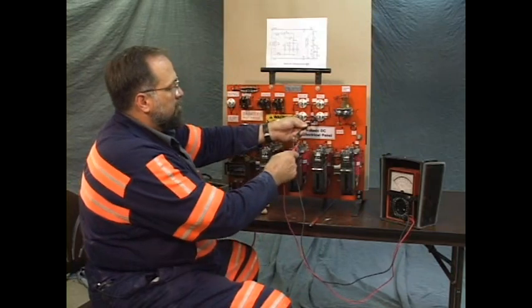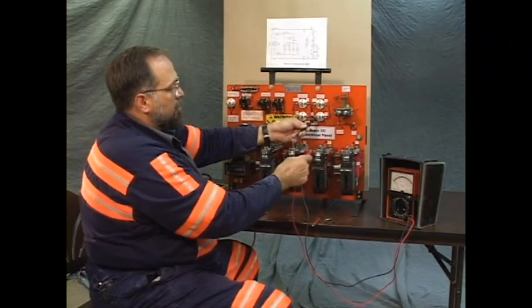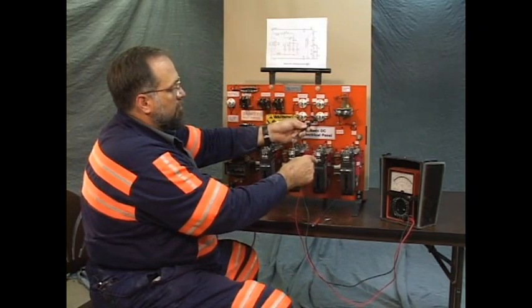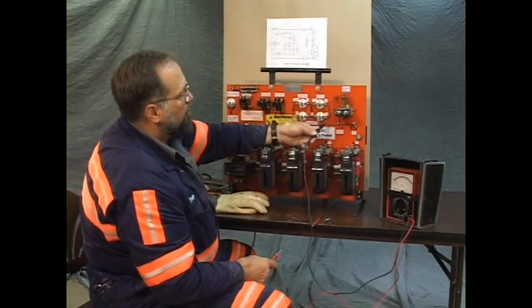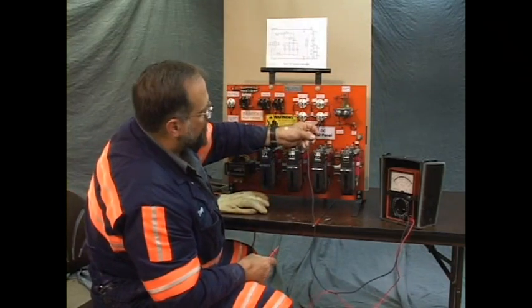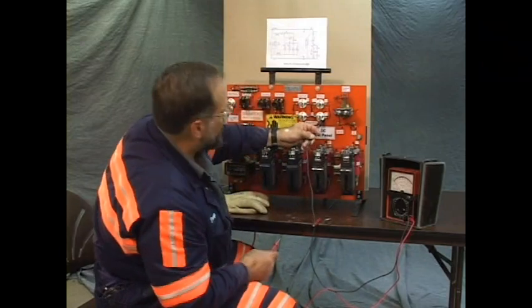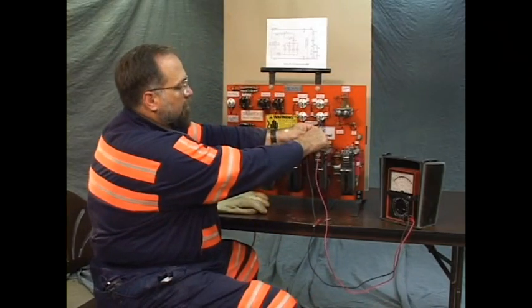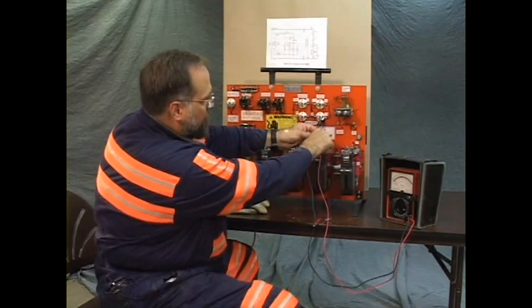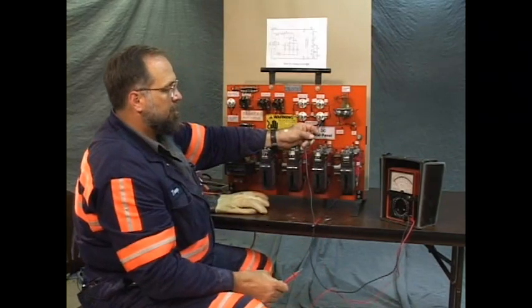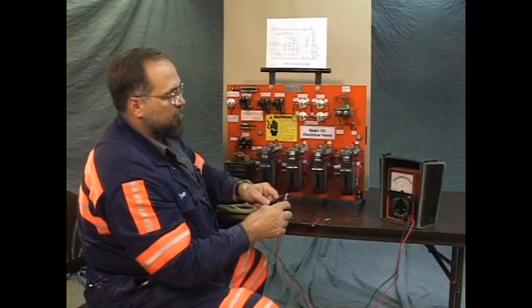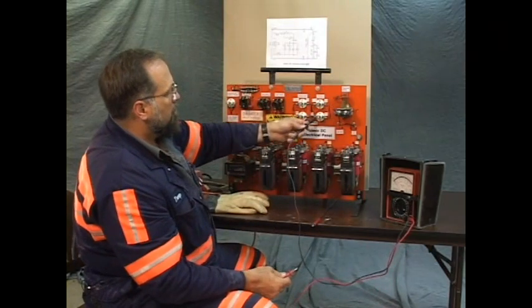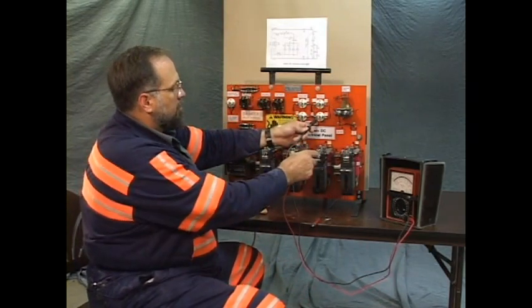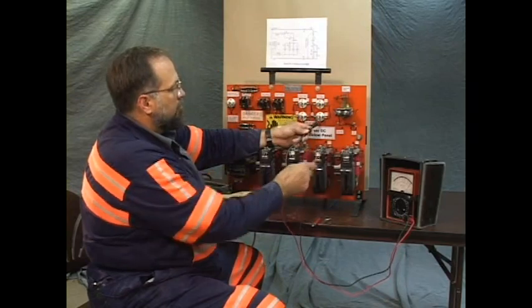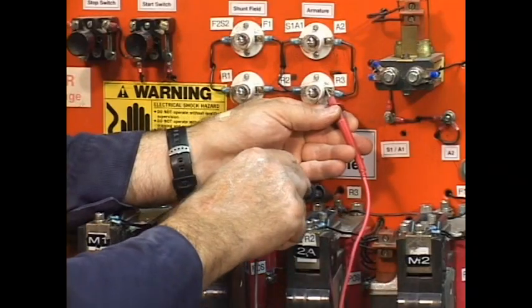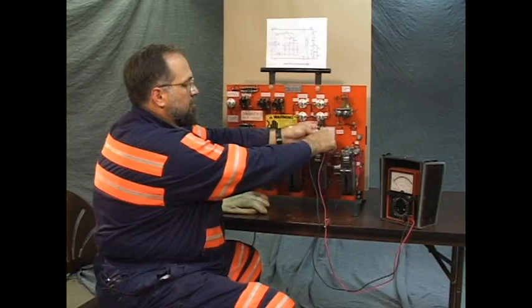If the left side of that resistance connects to the front of this contactor, by that we know that the right side of the resistance is to be connected to the rear of the contactor. But there's no reading. We're sure our meter is right, it's calibrated. We know that that's one side of the circuit. By default, this must be the other. It does not read.